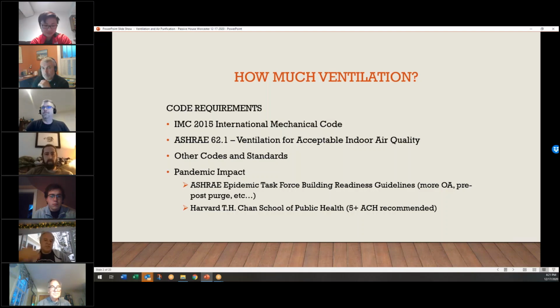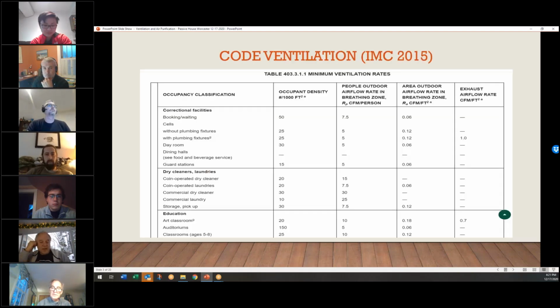If you go to the next slide, it's really cut right out of the IMC. This table has definitely changed over the years. I think back in the 6th edition of the code, it was probably just CFM per person. Then around the 7th or 8th edition, they adopted so much basically in these columns. Like if you look at educational at the very bottom, classrooms, 25 people per 1,000. Each person, you have to figure 10 CFM of outside air.